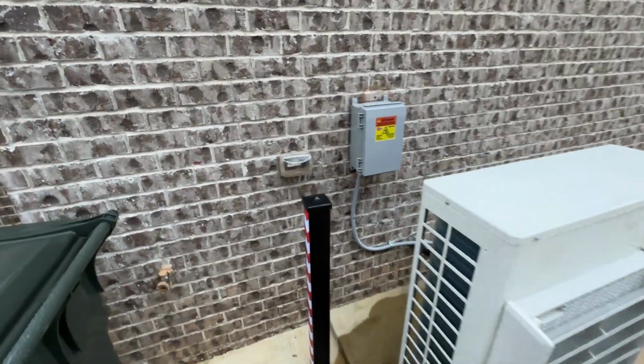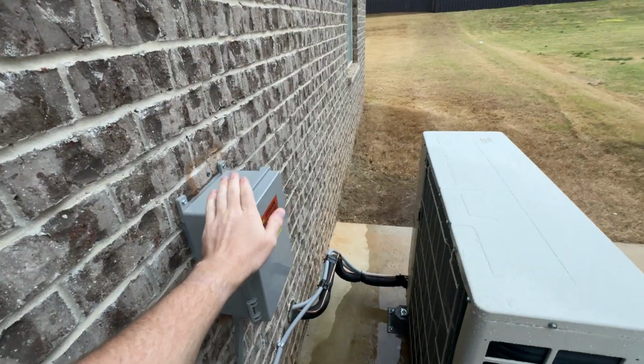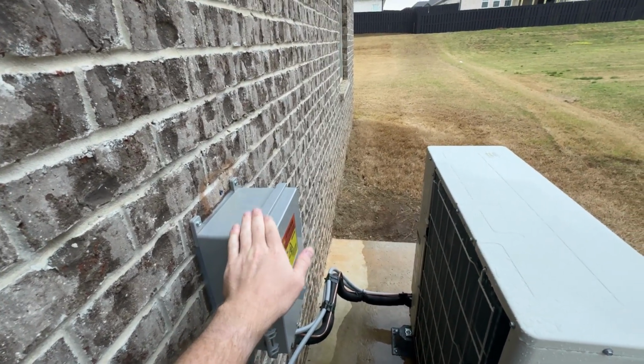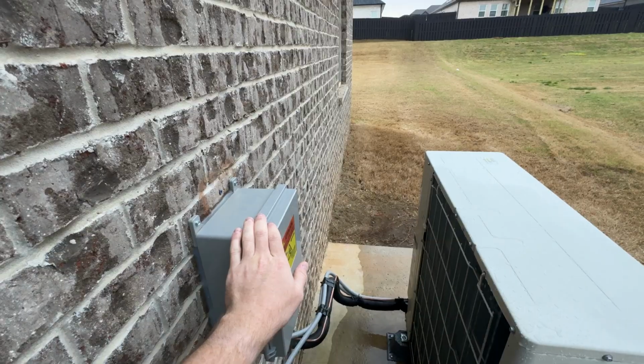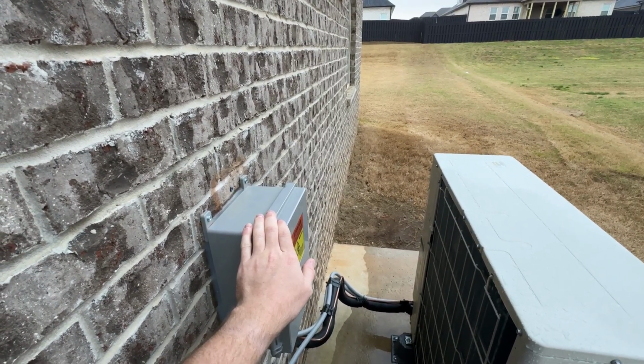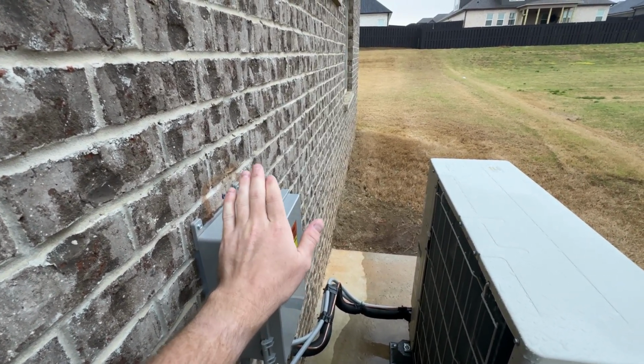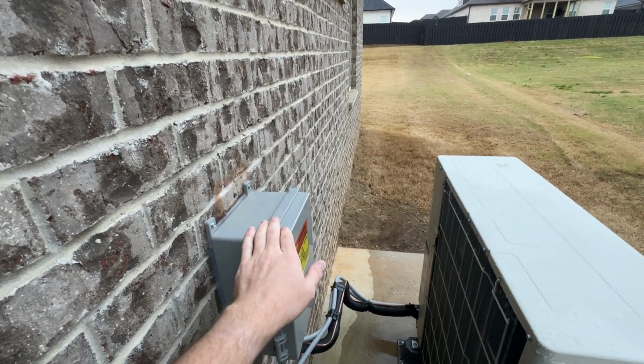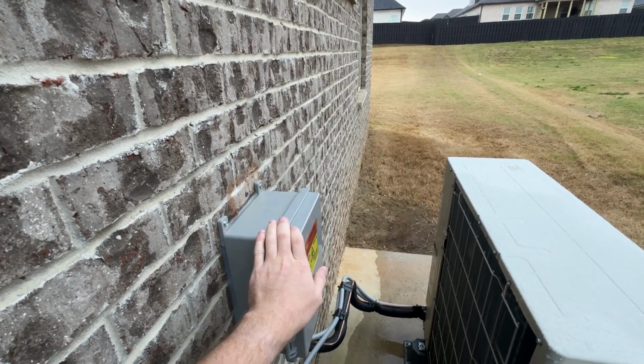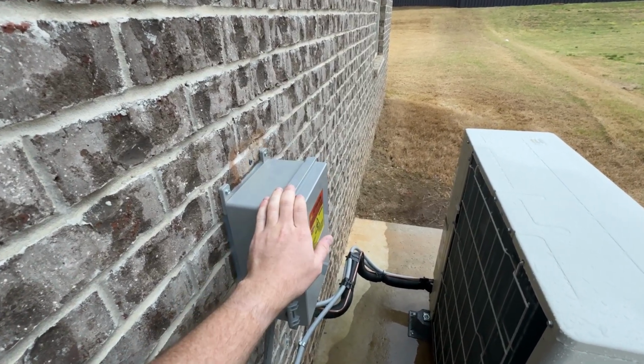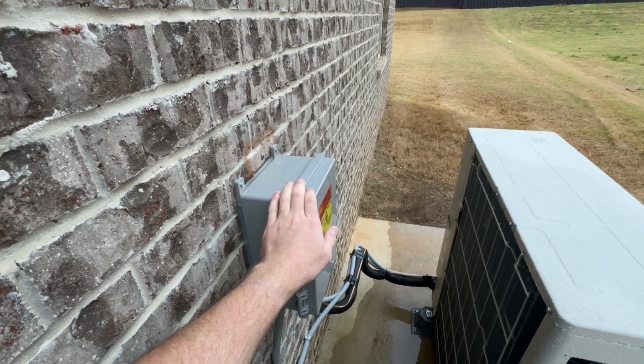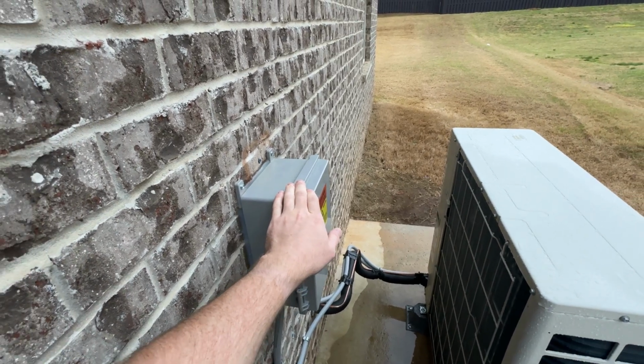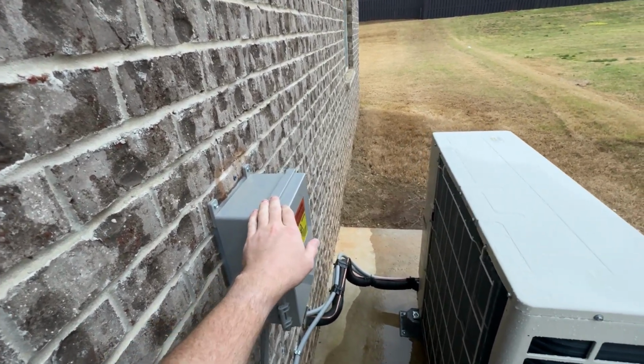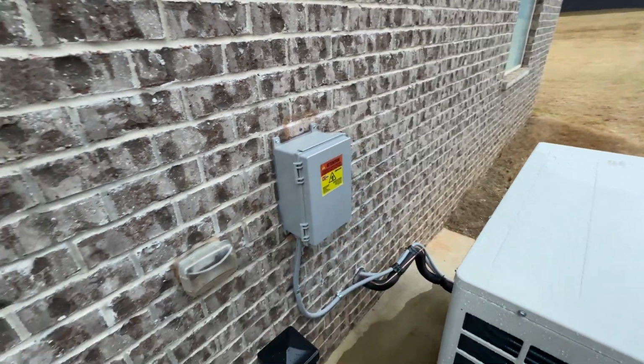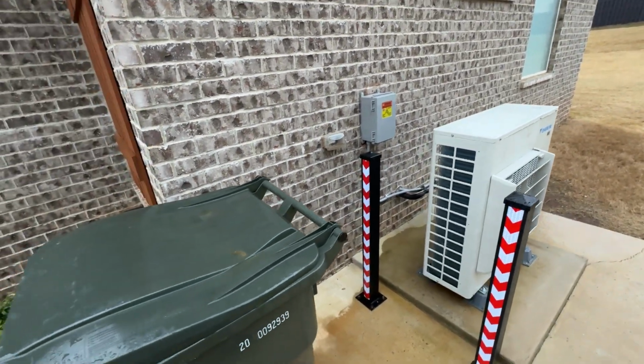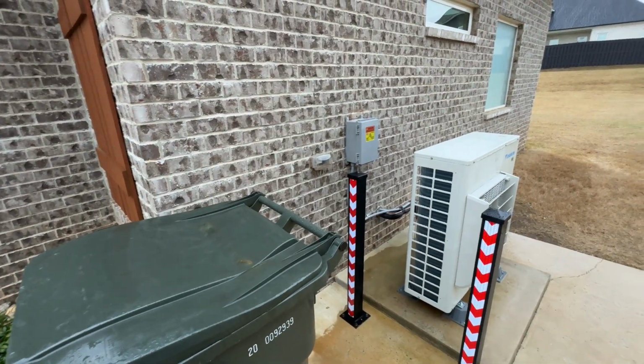And the thing you have to remember, the way this works, is that if it detects above 253 for more than 2 seconds, it'll trip. Then it starts a 2-minute countdown cycle, and every 2 minutes it looks for 2 minutes straight. If it sees above 253 another time, even for a split second within that 2-minute window, it's going to stay tripped. It's not going to turn the unit back on. And this stayed tripped for an hour and a half or longer, even till the crew was here, which tells me it was consistently above 253 at least once every 2 minutes for over 2 hours. And that's a problem, right?